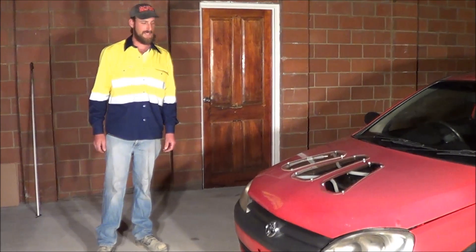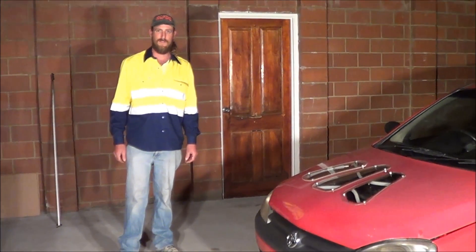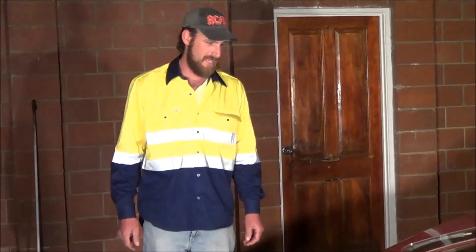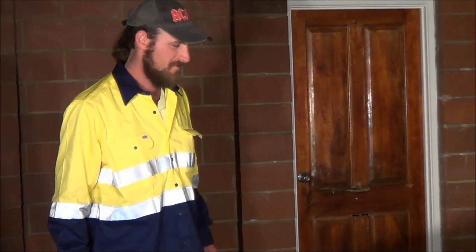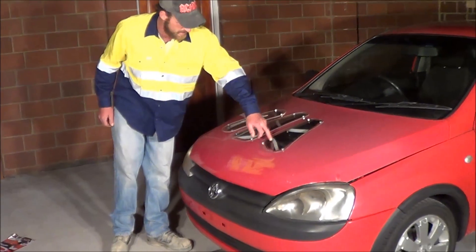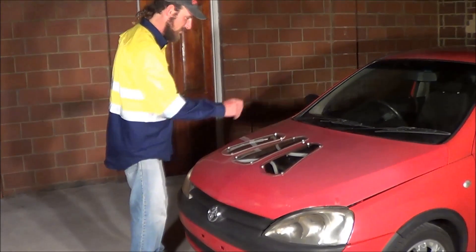G'day, today we're back here with the Blaze Cut fire suppression system. We're going to give this thing a go like I promised you. We're going to burn a car — exactly, this car is the one. It's a Holden Barina. We've set it all up, put the first X on the bonnet. You can see the system through there so we can see the flames as they come through.